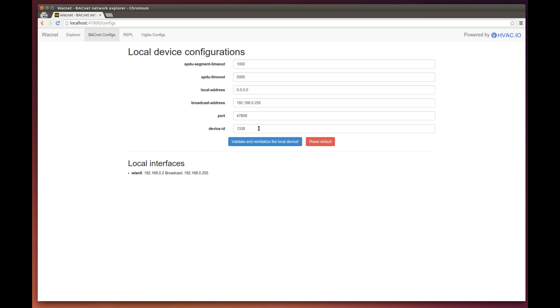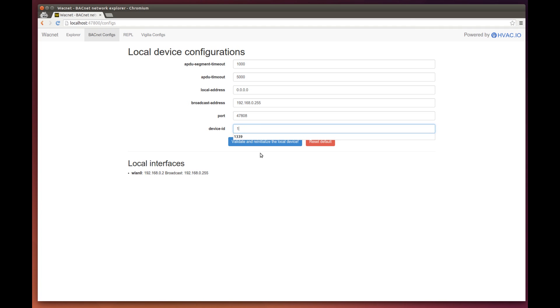In our case, WACnet is using the ID 1338. This means that no other device on the entire network can have the same ID. If you think you might be in the same range as other devices on your network, just pick something much farther away, something like 10,000.